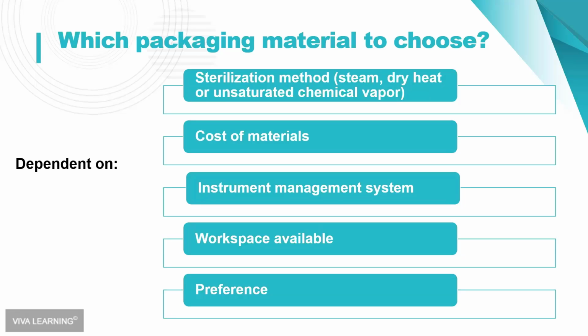What do I like? What don't I like about the particular methods that are available to me for packaging instruments? And the whole reason we are talking about packaging of instruments is that it is a requirement in the CDC guidelines that all items placed in heat sterilization must be packaged prior to sterilization. So this is sort of a change in some practices where they've used dry heat, where they typically didn't package, and in orthodontic practices where they chose, again, to use dry heat and didn't package and just took their instruments and put them maybe in a cassette, maybe in some kind of a holder, and didn't protect the sterility of those instruments once they came out of the sterilizer.